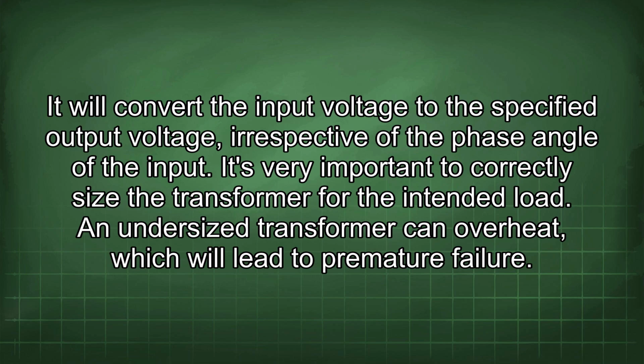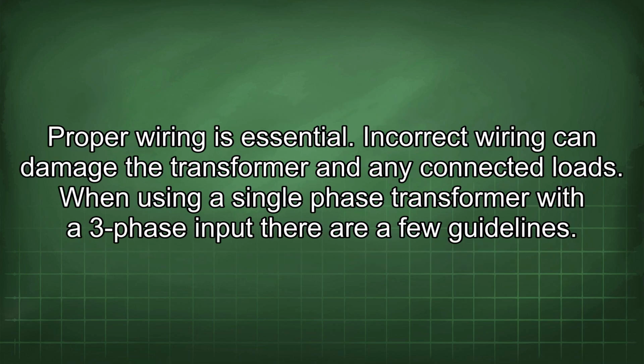It's very important to correctly size the transformer for the intended load. An undersized transformer can overheat, which will lead to premature failure. Proper wiring is essential. Incorrect wiring can damage the transformer and any connected loads. When using a single-phase transformer with a three-phase input, there are a few guidelines.